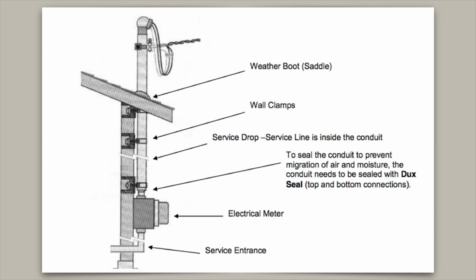The weatherhead is where the service wires enter into the conduit. Make sure that this area is in good repair. The wires should droop downward just before they enter the weatherhead. This is called the drip loop. The drip loop simply allows the water to fall off rather than entering through the weatherhead and down the conduit into the house.